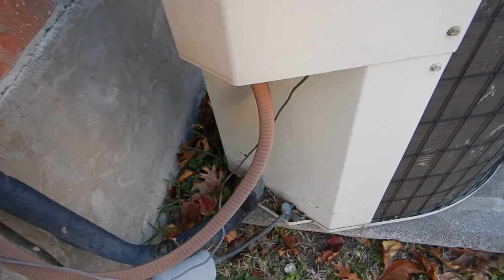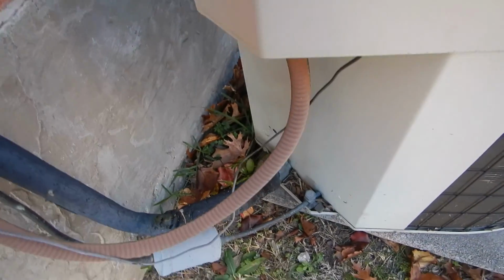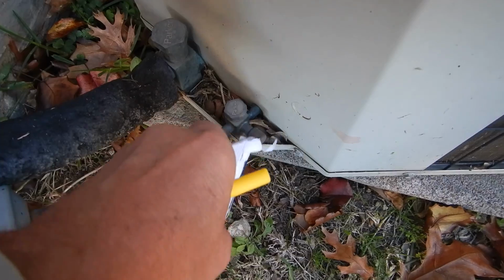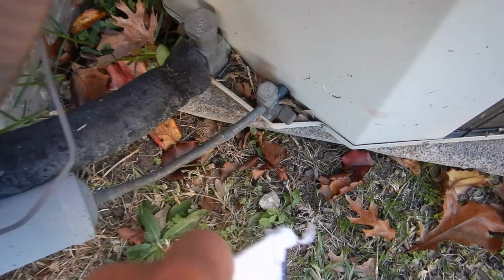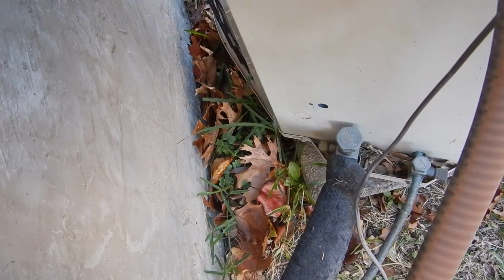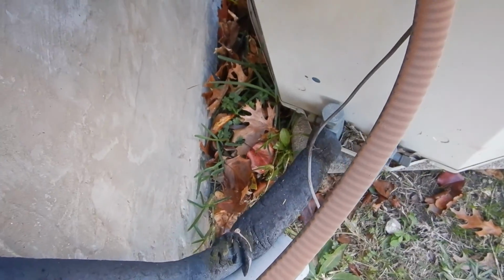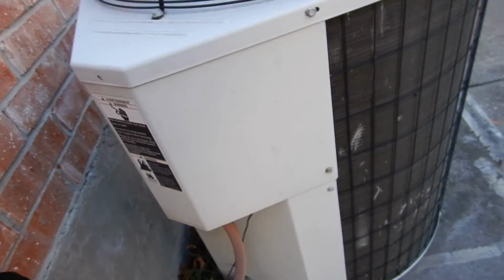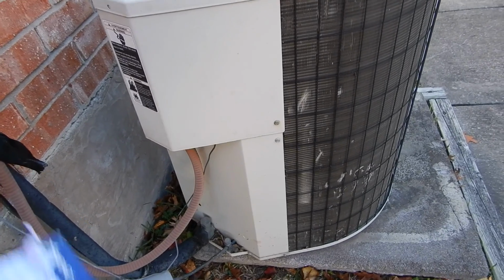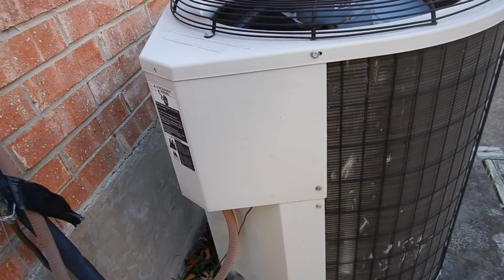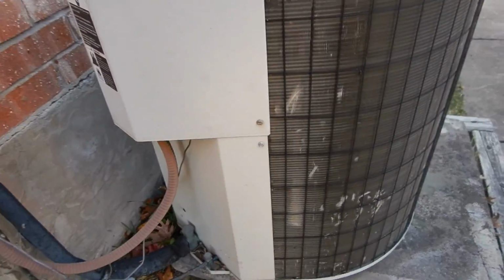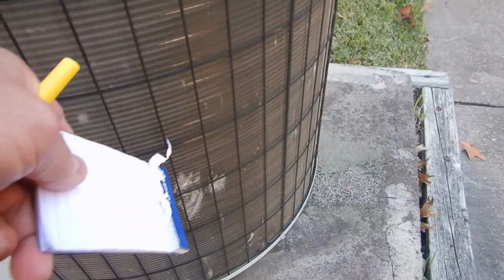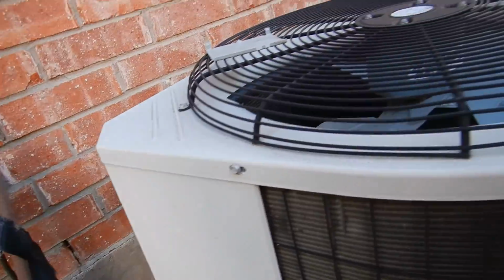Another thing that didn't exist when this system was installed, I don't think, was anti-theft Schrader valve caps. Look that up in the dictionary. Those Schrader valve caps keep kids from huffing the refrigerant and keep people from stealing it. Remember, this is R22. This stuff is gold. The refrigerant in here is worth more than the unit. But this is an older system, and it's the inspector's reasonable opinion that it would be prudent to budget for replacement. We got some bent coils in here, and again, I said this is organic.